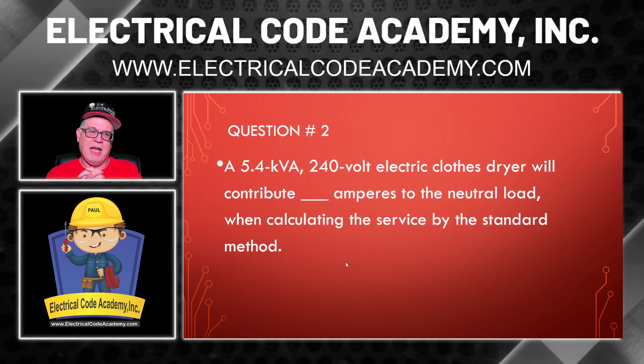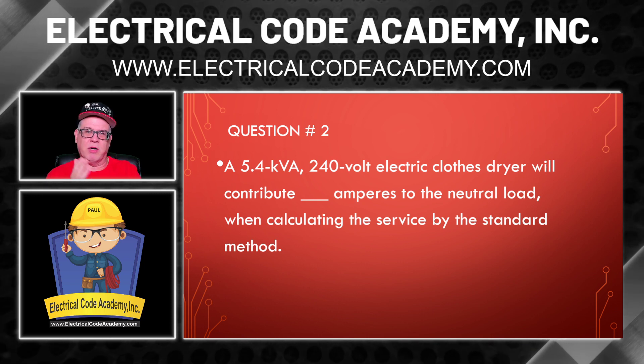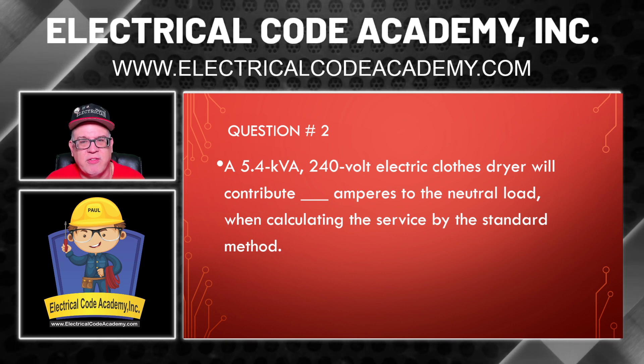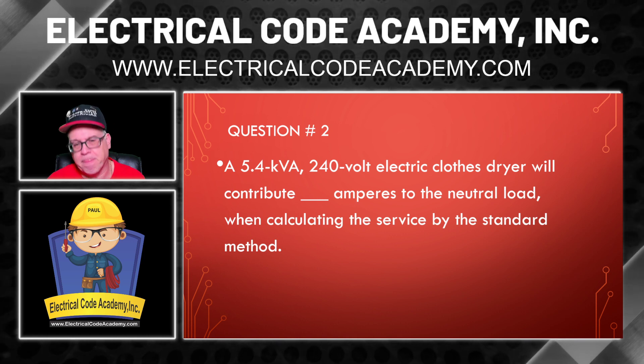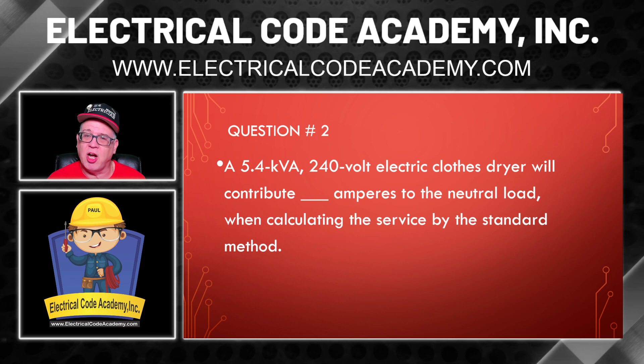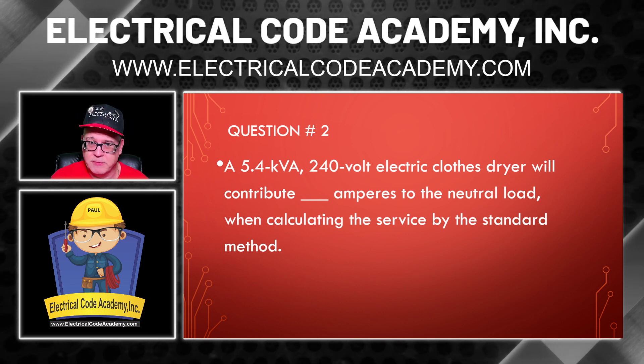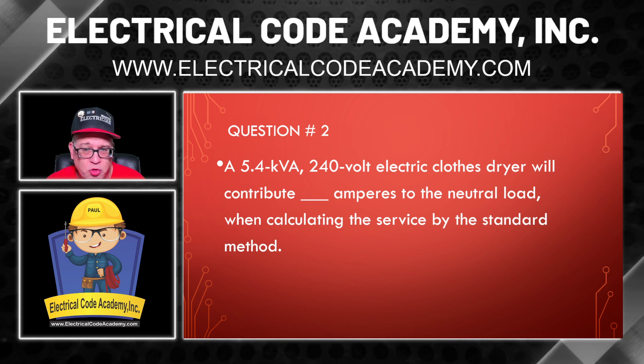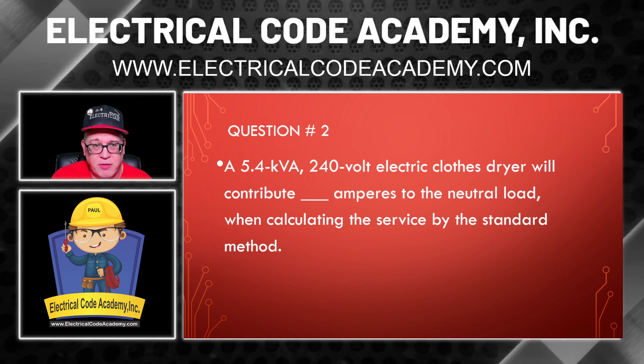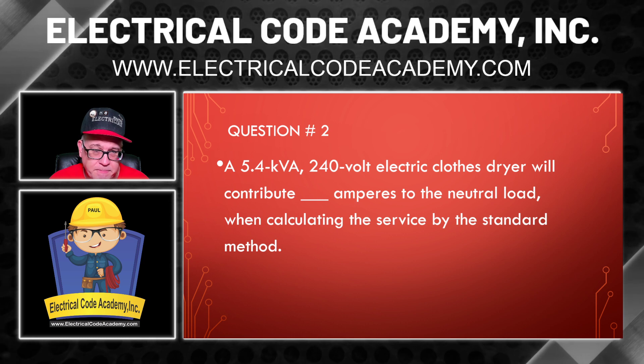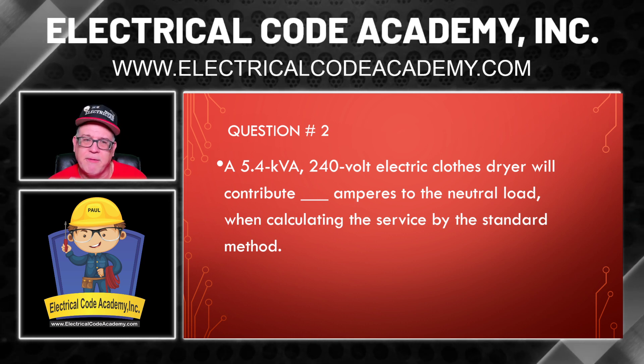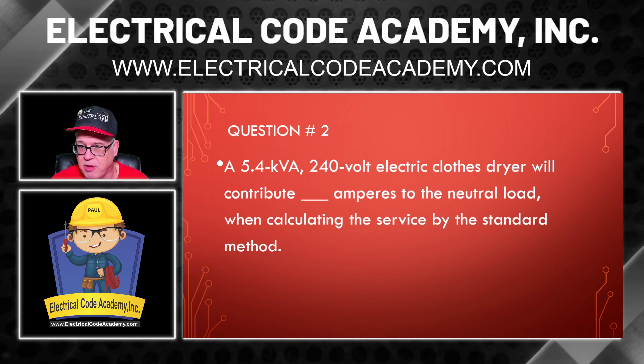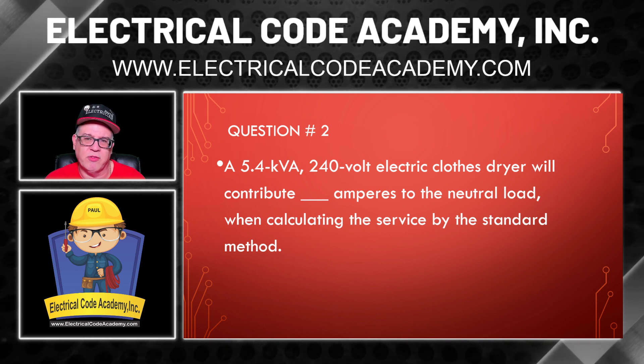Let's look at the next question. A 5.4 KVA 240-volt electric clothes dryer will contribute blank amperes to the neutral load when calculating the service by the standard method. We're calculating and looking for the contribution to the neutral load. The neutral is going to be less than what would be the ungrounded conductor value. I'm looking for amperes to the neutral load when doing this service under the standard method. So the first thing we want to look at is 220.54, which gives us the actual value we're going to use, and then we can look at 220.61B, which is for the neutral contribution.